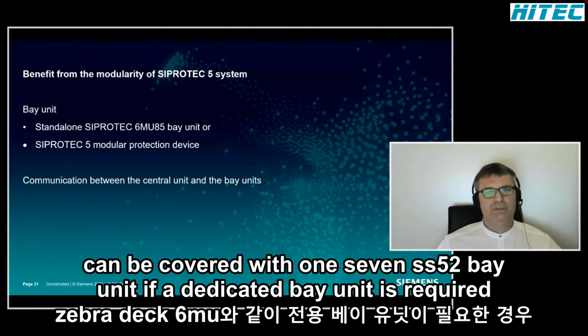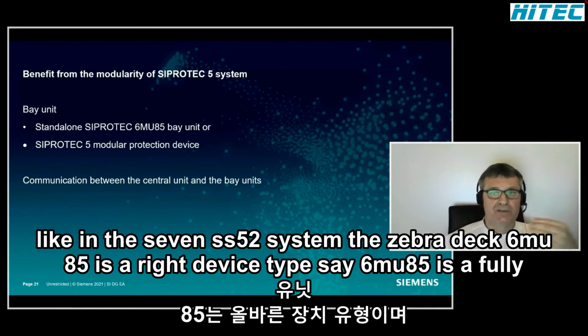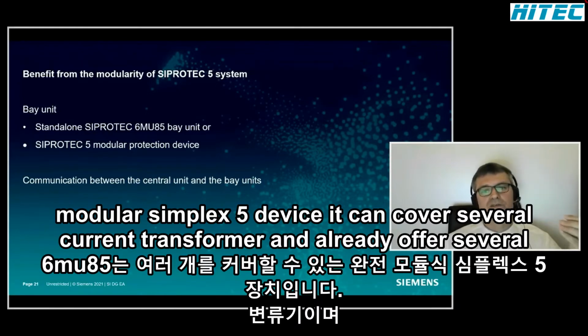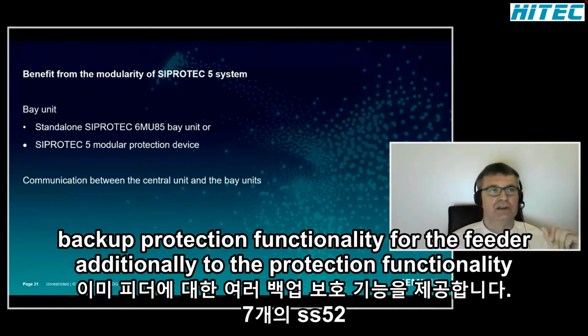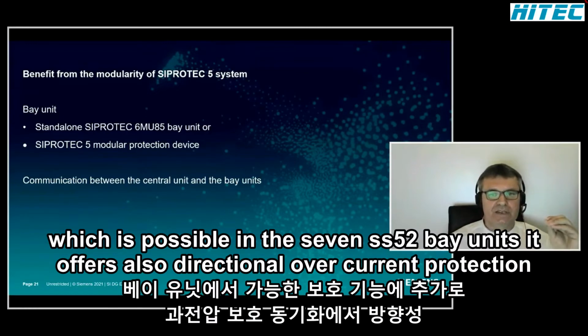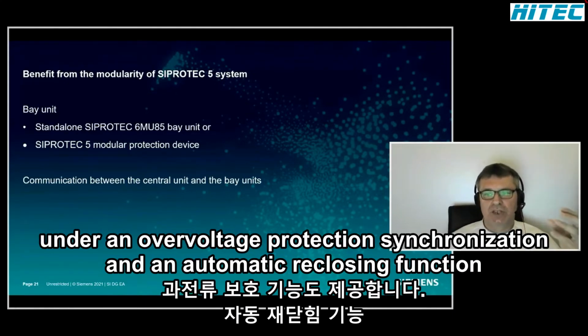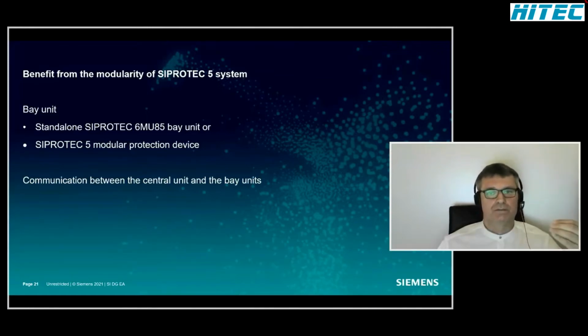If a dedicated bay unit is required, like in the 7SS52 system, the SIPROTEC 6MU85 is the right device type. The 6MU85 is a fully modular SIPROTEC 5 device. It can cover several current transformers and already offers several backup protection functionalities for the feeder. Additionally to the protection functionality which is possible in the 7SS52 bay units, it also offers directional overcurrent protection, under and over voltage protection, synchronization, and an automatic reclosing function.